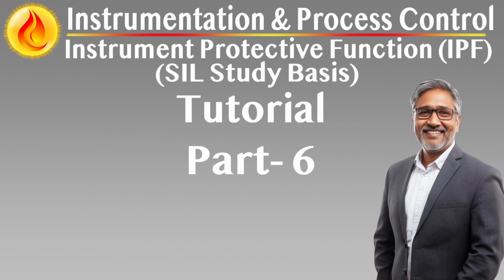Latency and determinism. For time-sensitive functions, communication delays must be accounted for. Non-deterministic or delayed systems, e.g., wireless Ethernet without QoS, may not be suitable for SIL-rated interaction. Testing and validation of interfaces.